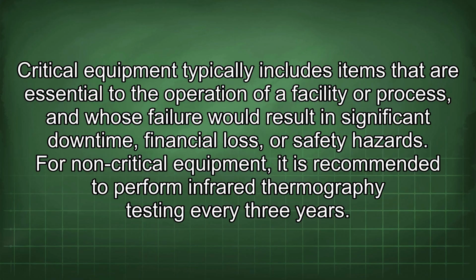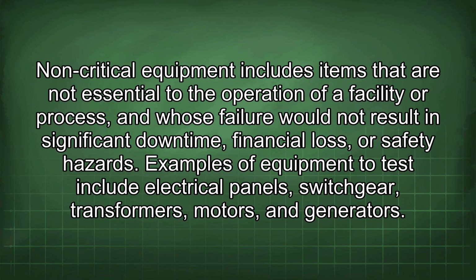For non-critical equipment, it is recommended to perform infrared thermography testing every 3 years. Non-critical equipment includes items that are not essential to the operation of a facility or process, and whose failure would not result in significant downtime, financial loss, or safety hazards. Examples of equipment to test include electrical panels, switchgear, transformers, motors, and generators.